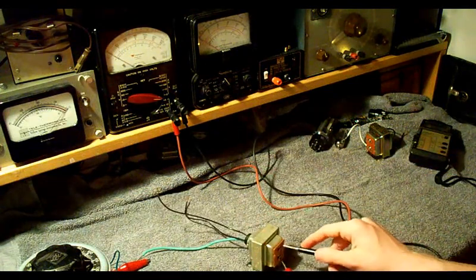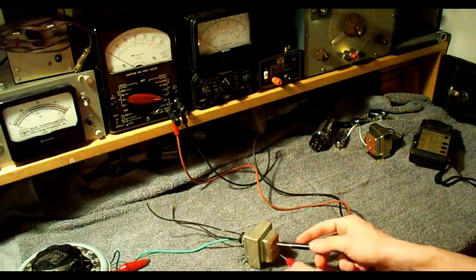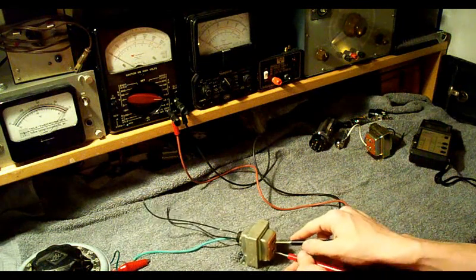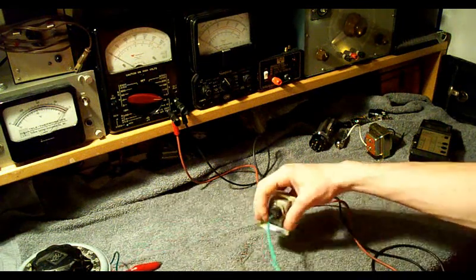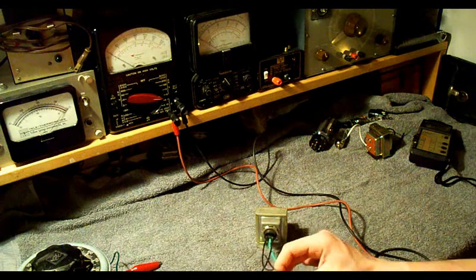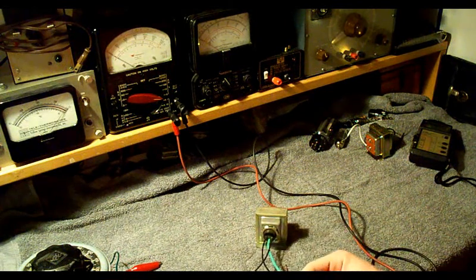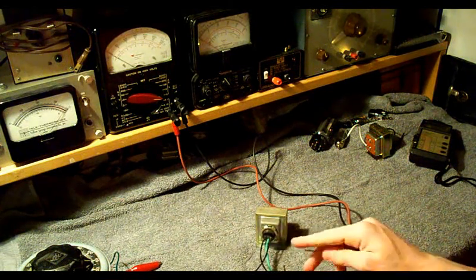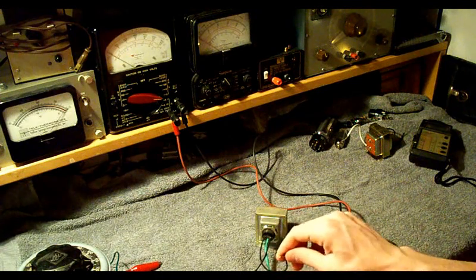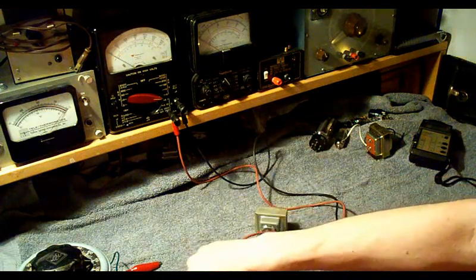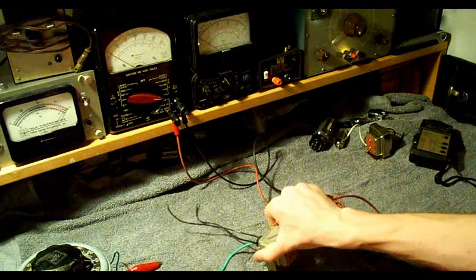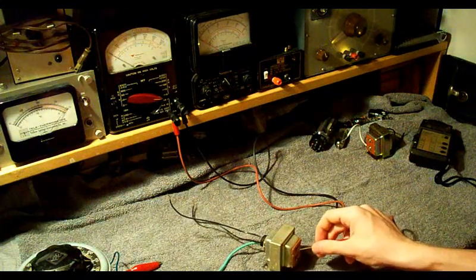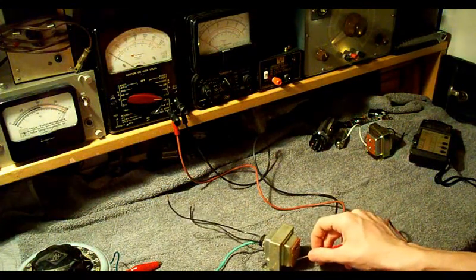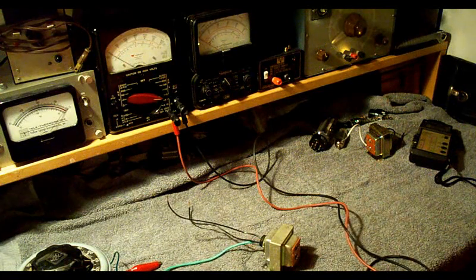So we're just going to check across the secondary winding, and that is also reading bad. So something's wrong with this transformer. So now we'll check the ground wire to one side of the primary and the other side. Nothing, so that's good. Now we'll check ground to the secondary. Nothing and nothing. So there's no ground faults in the transformer, so you're probably thinking, what's wrong?